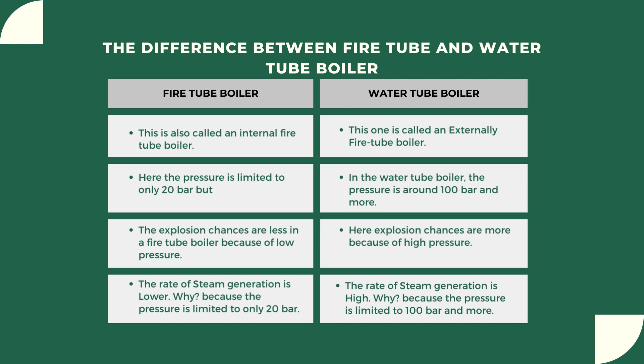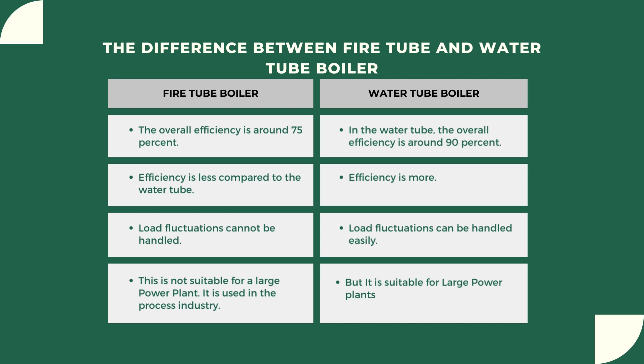The overall efficiency is around 75% in fire tube. In water tube boiler, the overall efficiency is around 90%. In fire tube boiler, the efficiency is less compared to water tube, and in water tube efficiency is more as compared to fire tube. Load fluctuation cannot be handled in fire tube. Load fluctuation can be easily handled in water tube. Fire tube is not suitable for a large power plant. It is used in the process industries, but water tube boiler is suitable for large power plants.